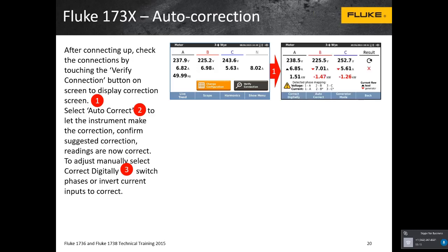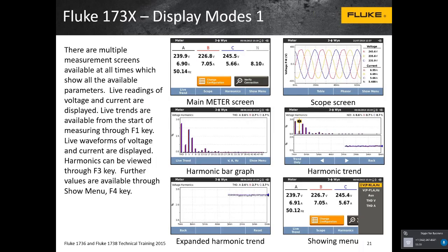With the 173X series, like the 1736 or 1738, you have the ability to not only capture event information but also graph it against a standard. The tool can take the data and put it up against trends like the ITIC and SEMI curves, so you can see where these fall relative to the operation of the electronic equipment—whether it's causing permanent damage, just operational problems, or is actually acceptable. You can trend this out in our Energy Analyze Plus software as well.